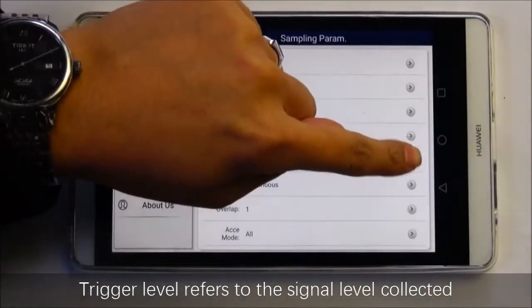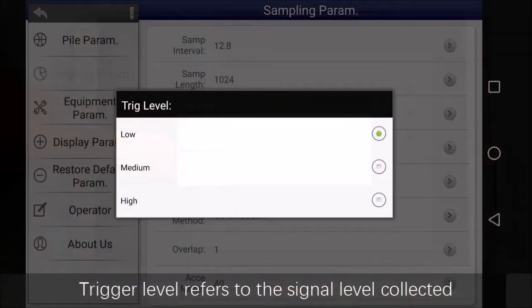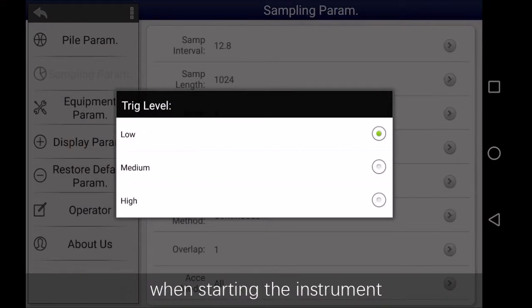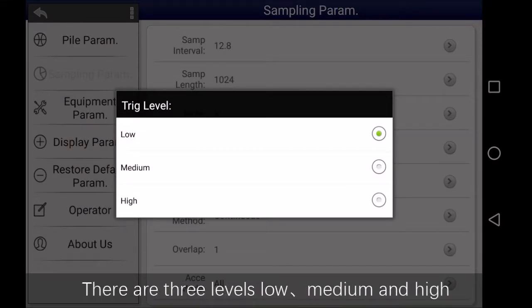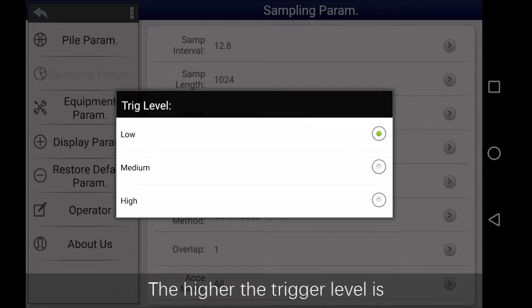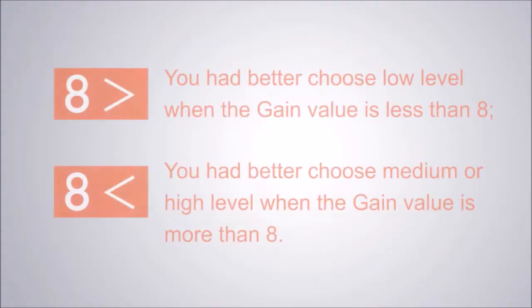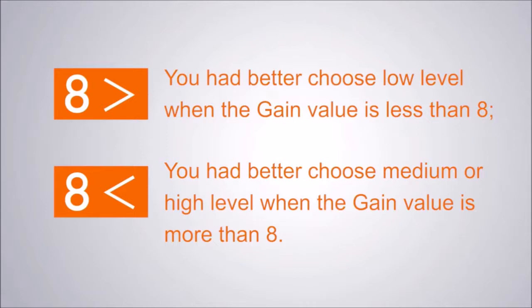Trigger level refers to the signal level collected when starting the instrument. There are three levels: low, medium, and high. The higher the trigger level is, the stronger the signal required. Generally, you'd better choose low level when the gain value is less than 8, and choose medium or high level when the gain value is more than 8.